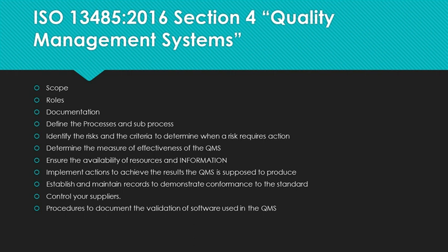Now, you're also going to have to consider documentation when you're developing the QMS. How is documentation going to occur? What is the format? Is it electronic, hard copy, in the cloud, video? How is it approved and modified? You have to consider and define the processes and subprocesses, and you have to include the input to each subprocess and process and the output, and the measurement method and interactions. You need to know if it's working or not. And if you change the processes, you have to look at and measure the impact of that change on the process and on the device.